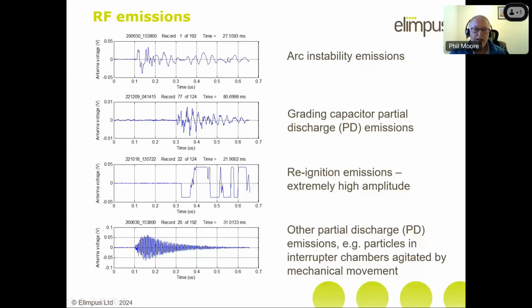And the reason you get this is that when you draw the arc and you blast it with gas to try and cool it down, the arc doesn't stay still. It moves around, it curls on itself, and then it connects with itself. It gets shorter, it gets longer, it changes its attachment points. And at all of these positions, it produces this RF emission.